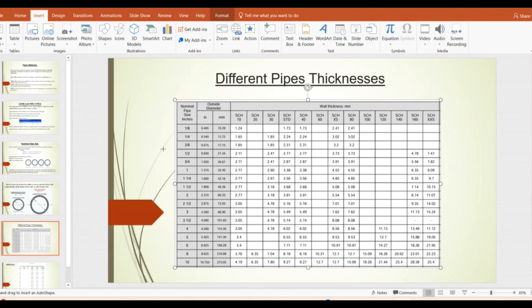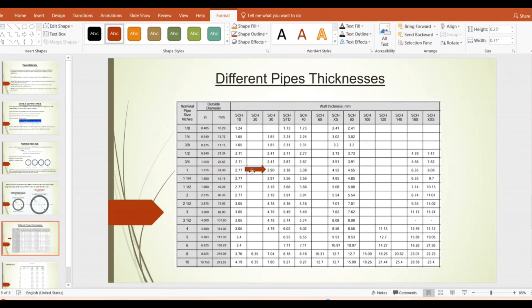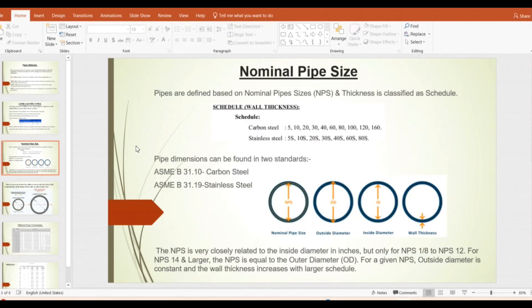Referring to the table: pipe sizes start from 1/8 inch to 10 inch and beyond. For a 1-inch pipe, the outer diameter is 1.315 inch, which equals 33.40 mm. For Schedule 10, the wall thickness is 2.77 mm; for Schedule 30 it is 2.90 mm — so as the schedule number increases, the wall thickness increases. For Schedule 40 it is 3.38 mm; for extra strength it is 4.55 mm; for Schedule 120 it is 6.35 mm.